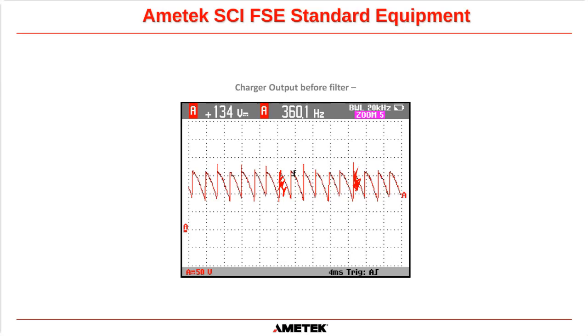But if we look at it with our oscilloscope, we can see straight away that that is missing, and we can say, okay, it looks like there's a gate lead loose or missing from one of the SCRs on the rectifier bridge, and therefore we can replace it before it causes any issues. And we have seen that multiple times. We have seen either, especially on startups, because our systems are transported over ground, and unfortunately we all know that the interstate highway systems in the US is not what it quite used to be.